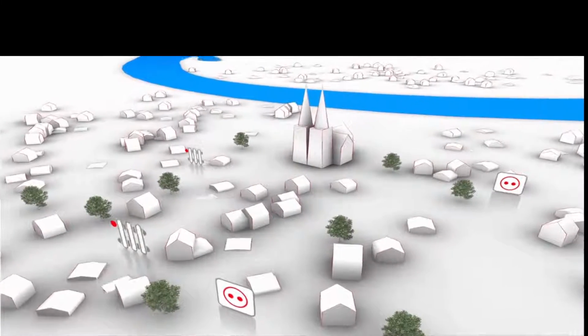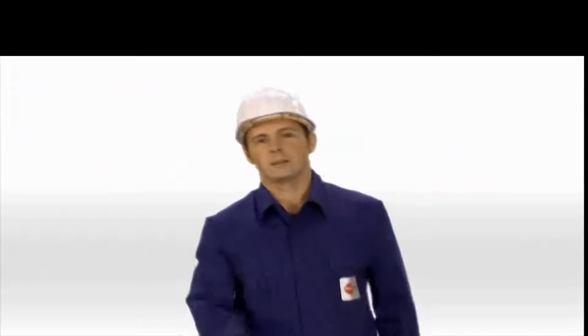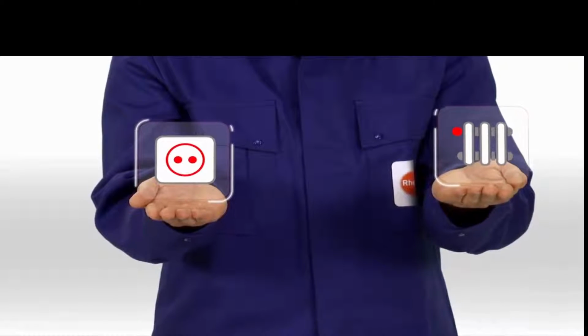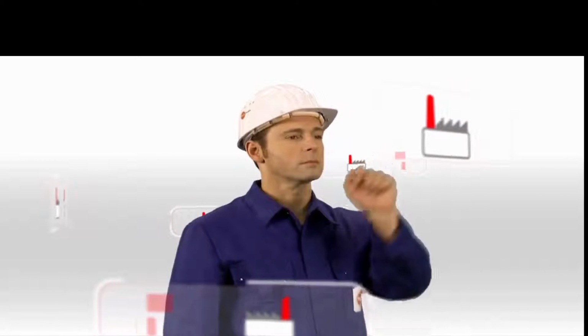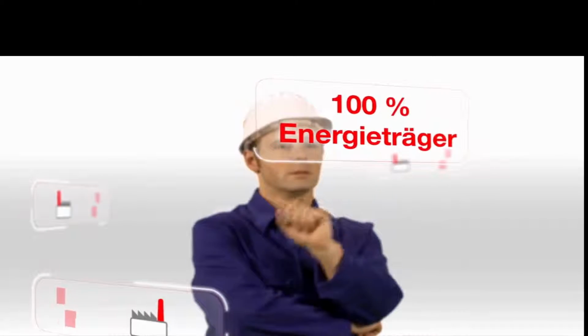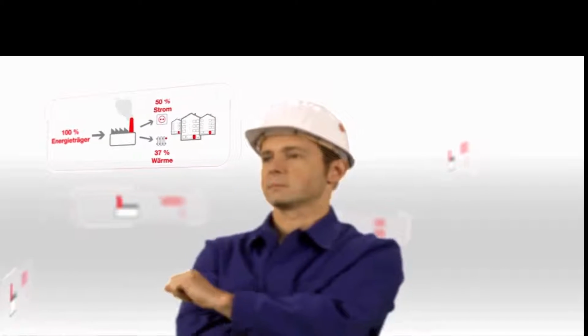Today we want to reveal something about the efficient use of energy, from which not only many customers of Rhein Energie have been profiting for years, but also the climate. In our Cologne power plants, we use natural gas as fuel, and this not only generates electricity, but also district heat. The clever process is called cogeneration. We use the technology in our power stations, producing 50% electricity and up to 37% heat out of 100% used energy. Therefore, only 13% of the input energy is unused. In the case of conventional power plants, which generate only electricity, around 60% of the input energy is lost.